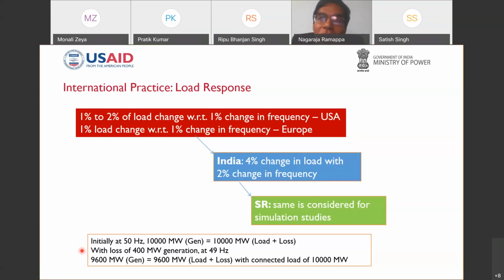What will happen? Frequency starts falling. But my connected load is still 10,000 megawatt. Connected load is still 10,000 megawatt, but the frequency starts falling in the expression H by pi f d omega by dt is equal to Pm minus Pe. In that expression, Pm minus Pe, there is a mismatch, so frequency starts falling.